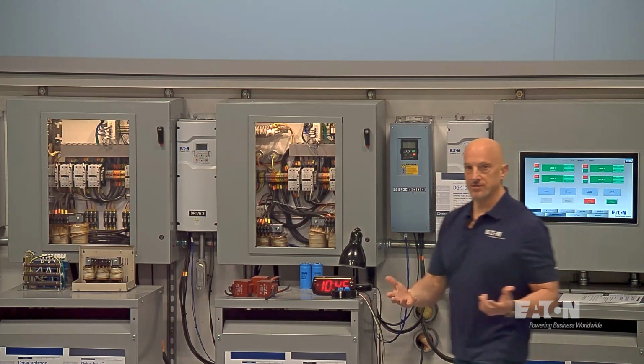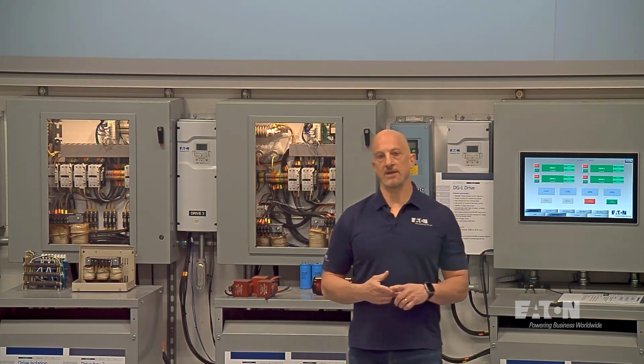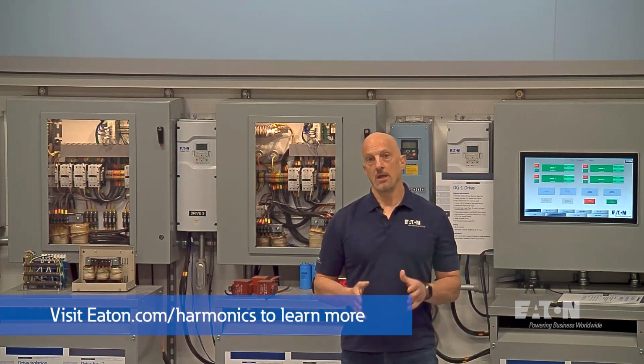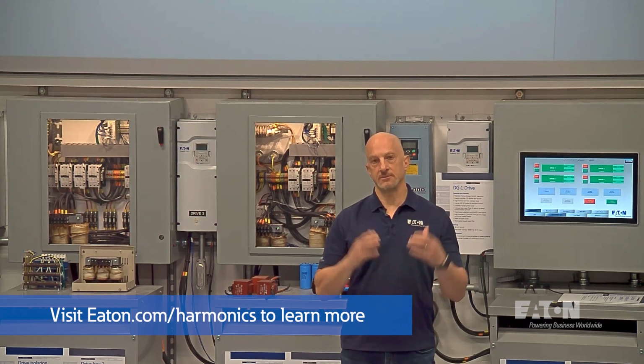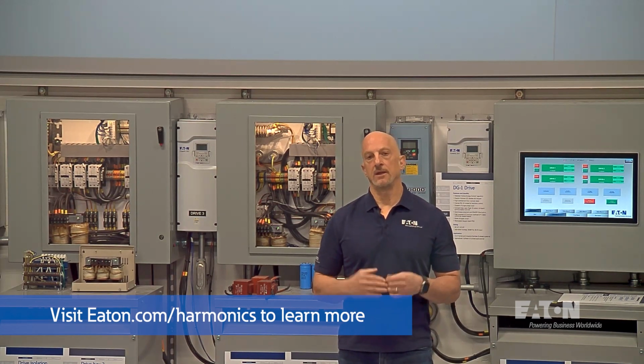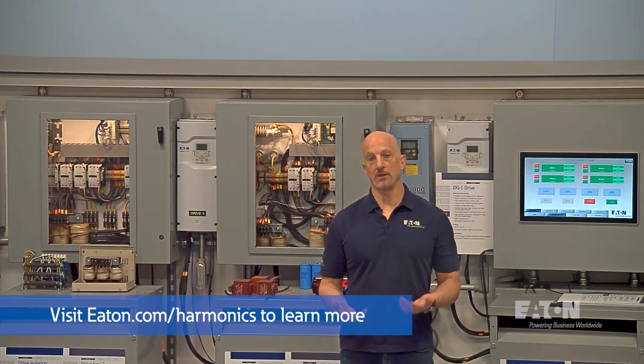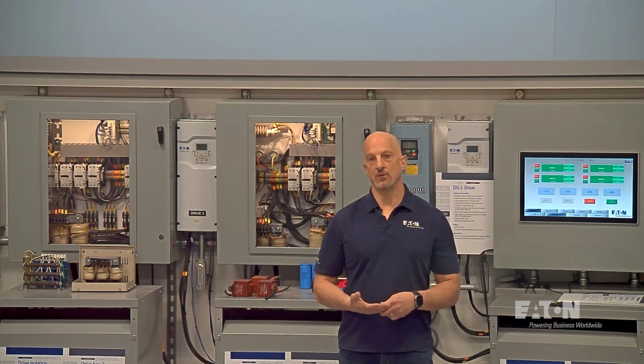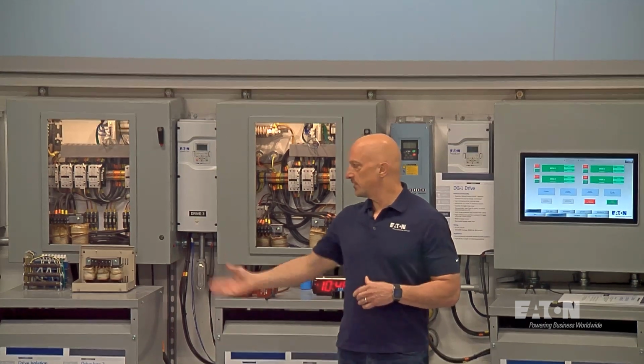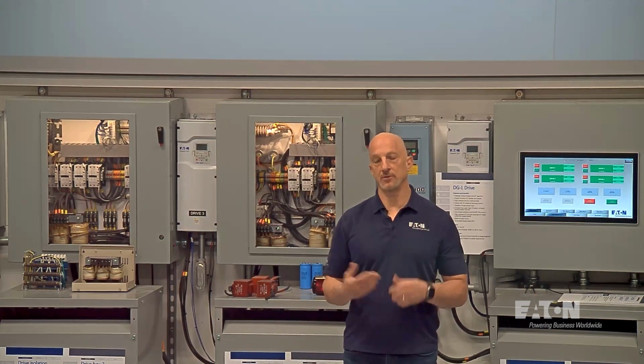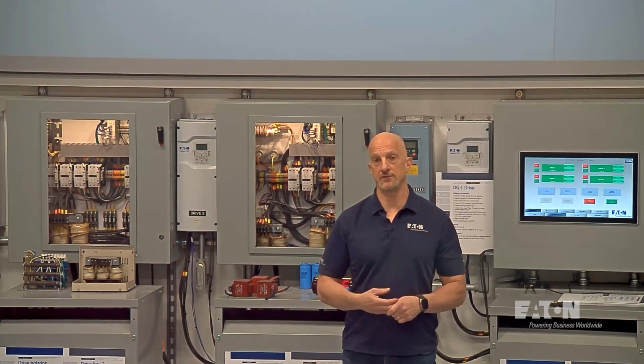So to answer the question again, do harmonics cancel naturally? No, they don't. What happens is power systems reduce the amount of harmonic current that's allowed to flow as you add more and more harmonic load. That's the natural form of impedance that's affecting you. But they can cancel when you use a purposefully phase shifting transformer or impose some sort of phase shifting on the power system.